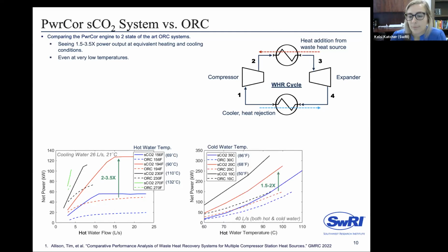Similar results if we look at a separate ORC vendor. Here the results are presented a little differently, with hot water temperature swept on the x-axis, and the various traces representing cooling water temperature. Looking at the light blue curve on the cycle diagram, and holding the water flow rates on the hot and cold streams both at 40 liters per second, we still see very similar results, with maybe 2 times as much power output using an SCO2 cycle versus ORC.